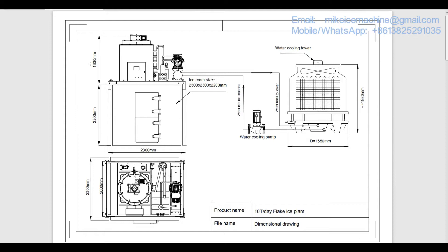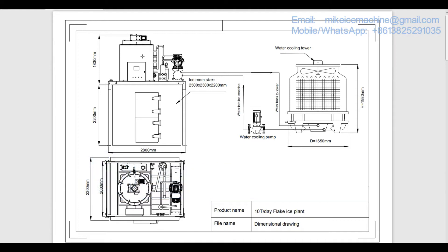This drawing shows a standard 10 ton per day flake ice plant. This machine can make 10 tons of ice flakes within every 24 hours. That capacity of 10 tons per day is based on working with 30 degrees Celsius ambient temperature and 20 degrees Celsius water inlet temperature.